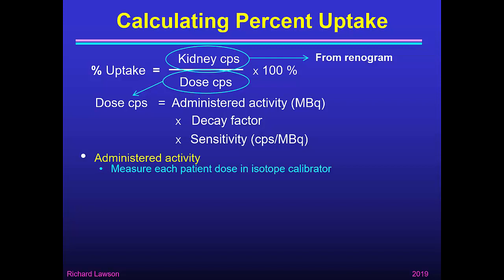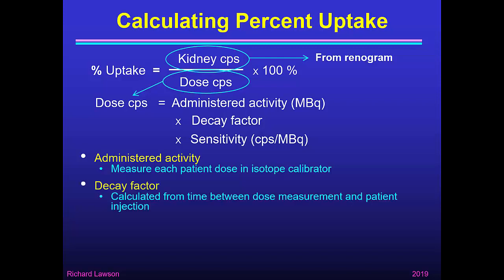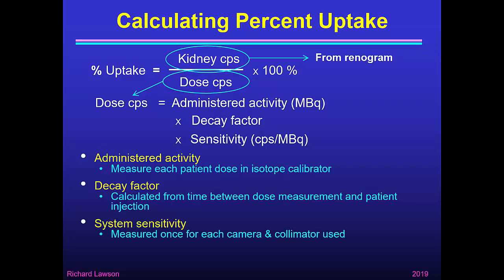We should know the administered activity because we measure each patient dose in an isotope calibrator before injection as a matter of routine, so that doesn't require any additional work. The decay factor is calculated from the time between dose measurement and patient injection, which is easy because we know that time and we know the half-life of the radionuclide, which is usually technetium-99m. So all we need to know is the system sensitivity, which can be measured once for each gamma camera and collimator used for renography.